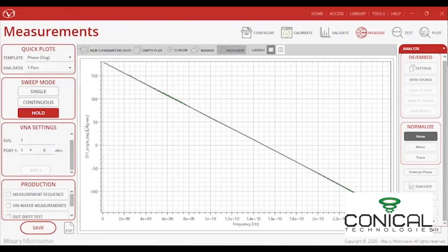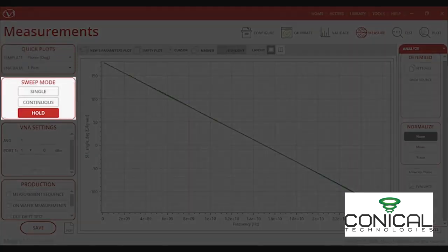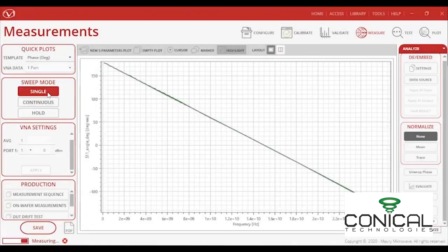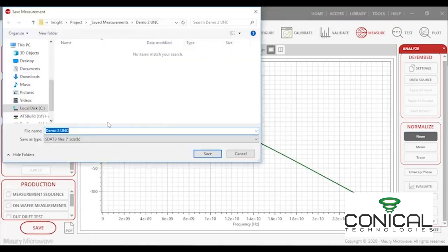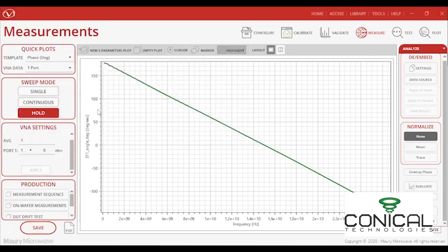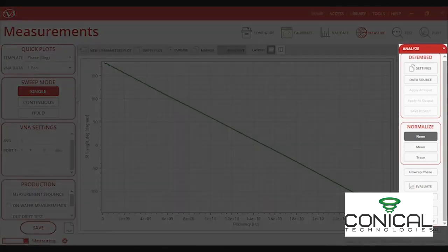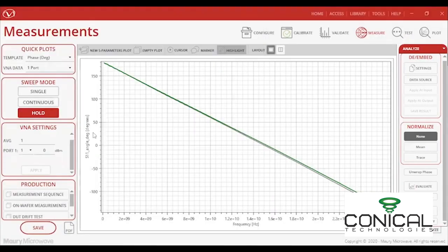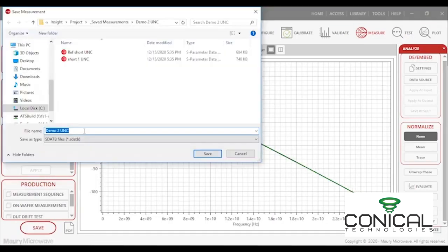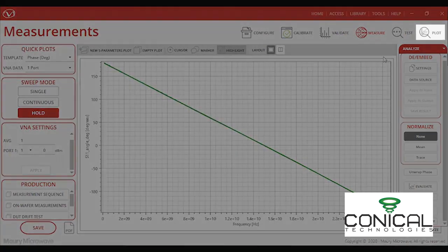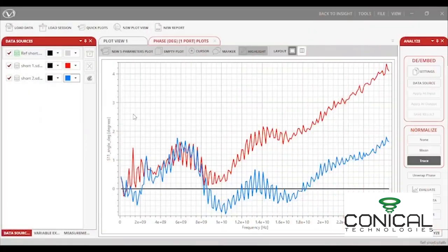In the Measurements tab, I can select from a list of quick plots, set the sweep mode, and configure the averaging and port power of the measurement. There is also an uncertainty section that can display the total uncertainty budget and the individual contributions from the equipment, which I will cover more in depth in the plot module. And lastly, there is the Analyze section, which allows the user to de-embed, normalize traces, unwrap phase, and more. Before I move on to the plot module, I'll quickly obtain some data of a 24-inch Maury Stability Plus cable connected over to a short standard. Let's jump right into the plot module next.